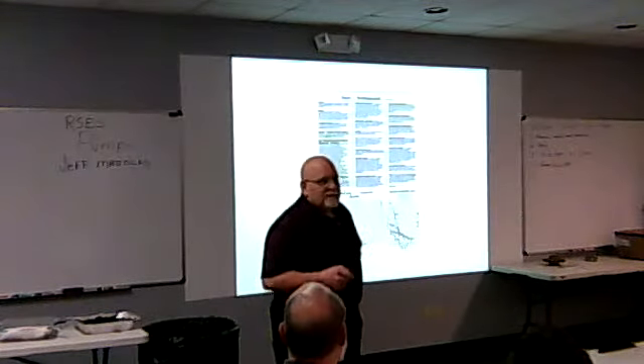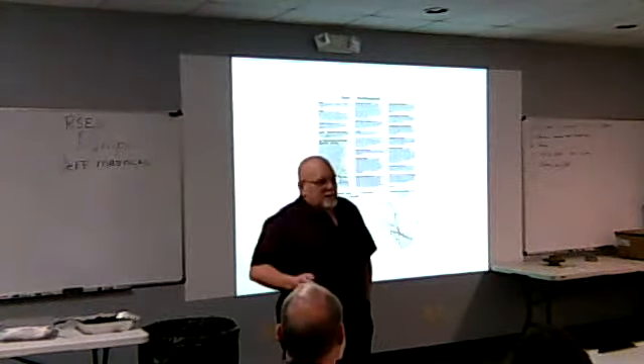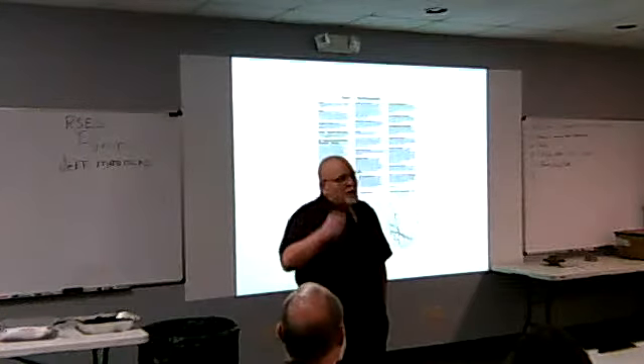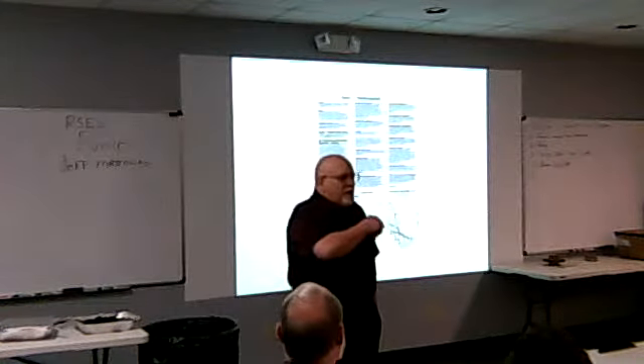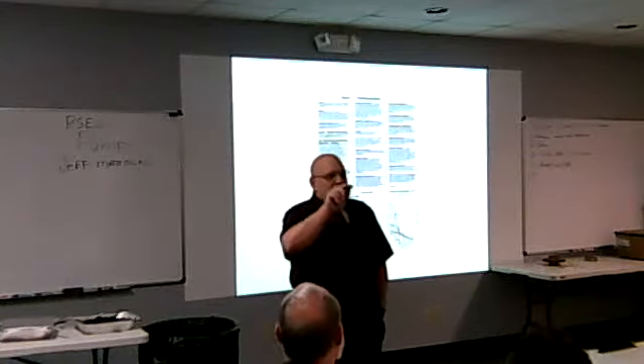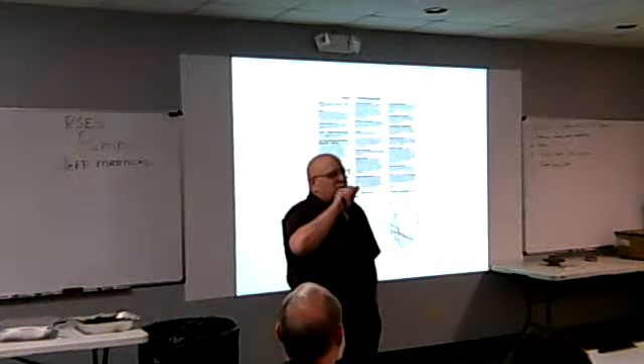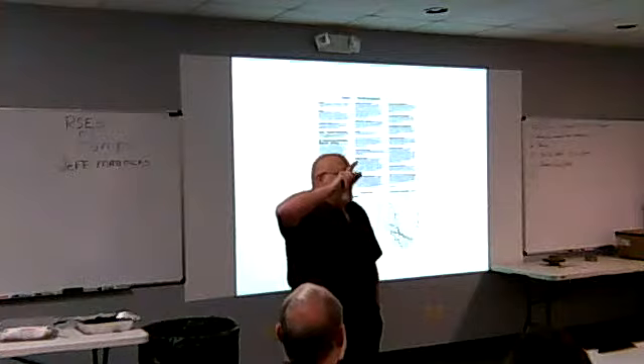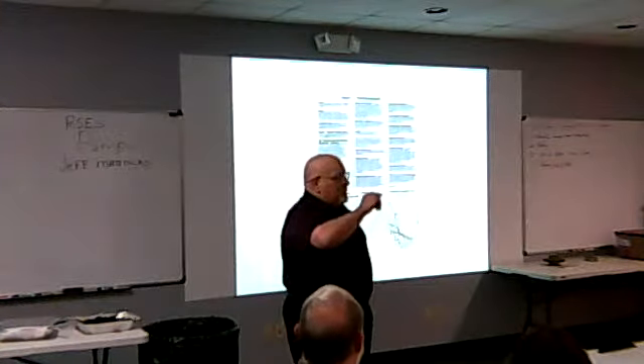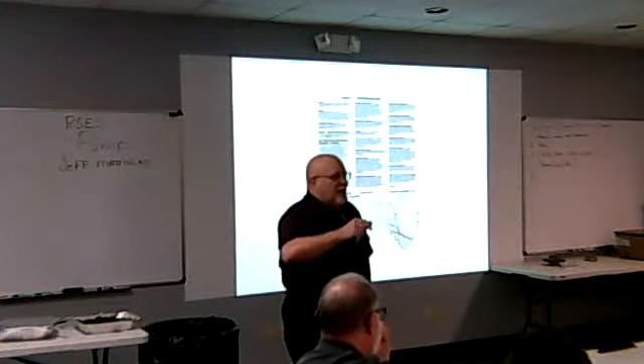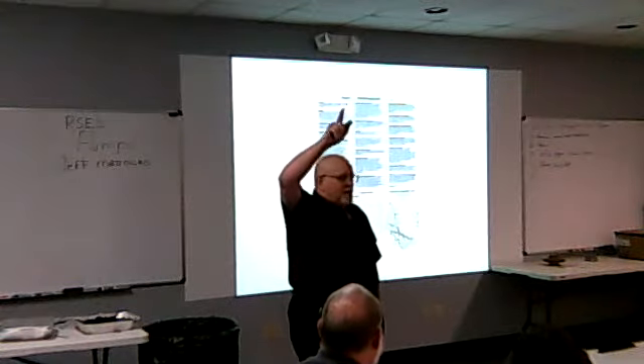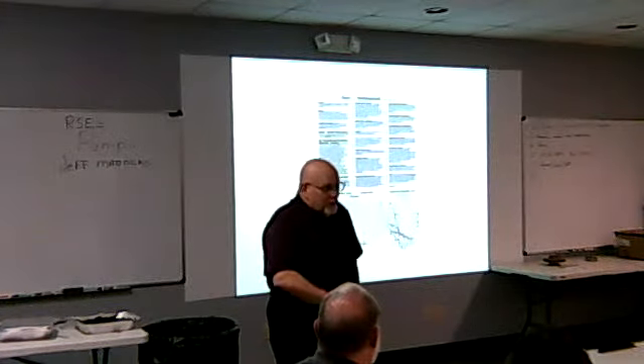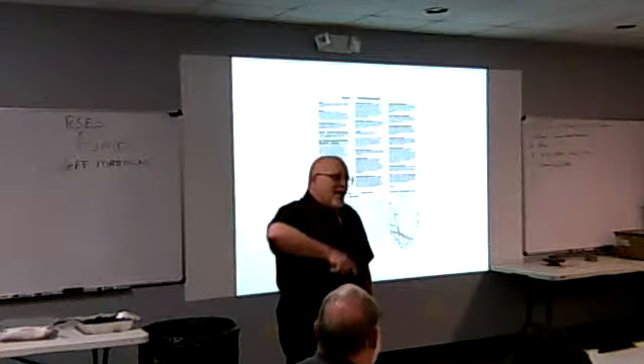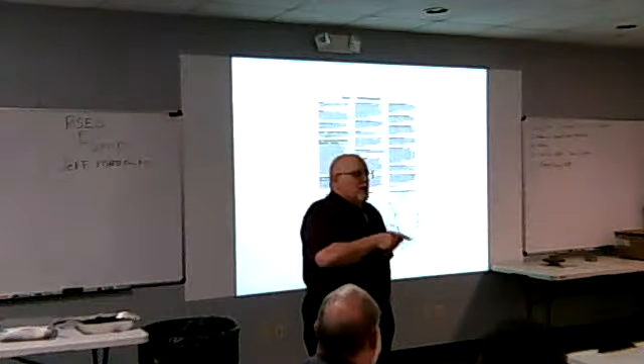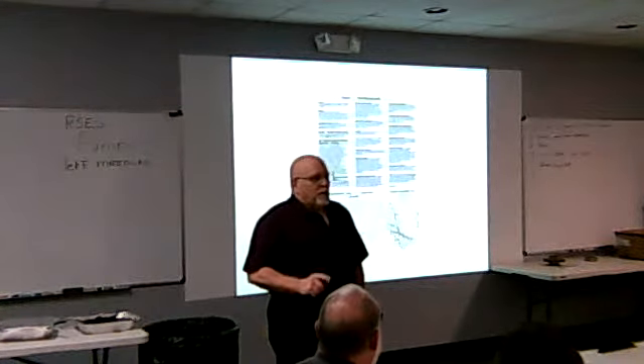I had so many people call me and they say, you know, I've got a 5-story building, in a closed hydronic loop. All this pump does is overcome friction. Your fill pressure fills the loop. You get 1 or 2 PSI on the top floor. And this pump is just given enough to take the friction. I don't have to lift 5 stories. Now, if it's a domestic water booster system where I have an open tap, now I have to worry about the lift. But in closed loop hydronics, don't ever worry about the lift.